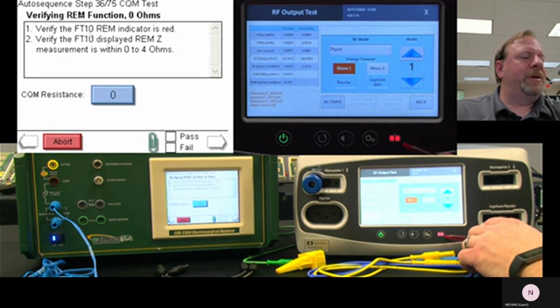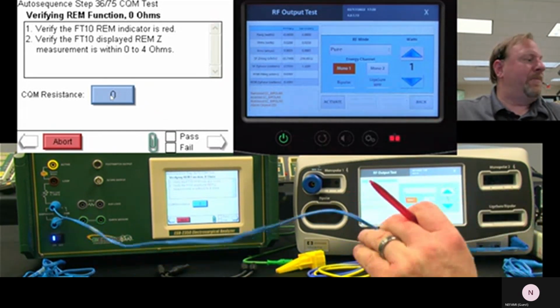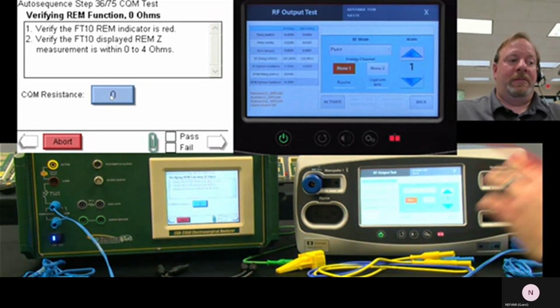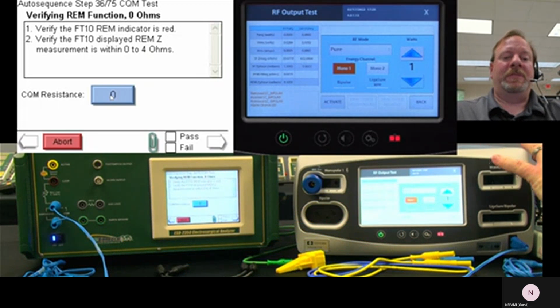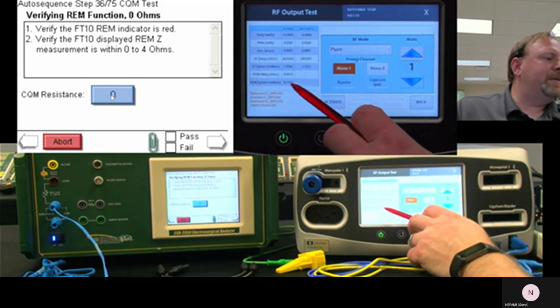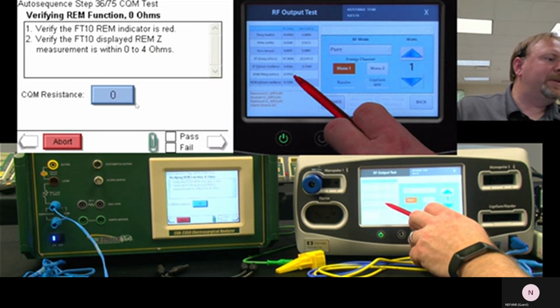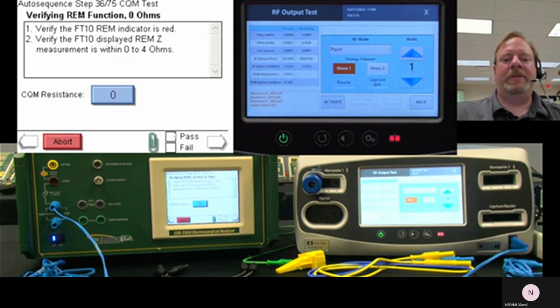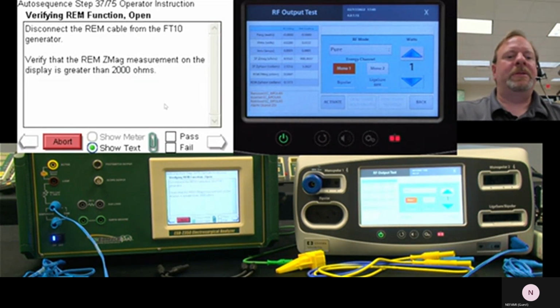REM indicator should turn red. So we've changed to 0 ohms. Again, that's saying that I put in a cable that's shorted. Covidien is saying you have to use a split pad. Split pads can't have 0 ohms. And in this case, measuring that short, that 0 ohms, we're getting 0.6, 0.7 ohms. So that's good. Thank you very much.